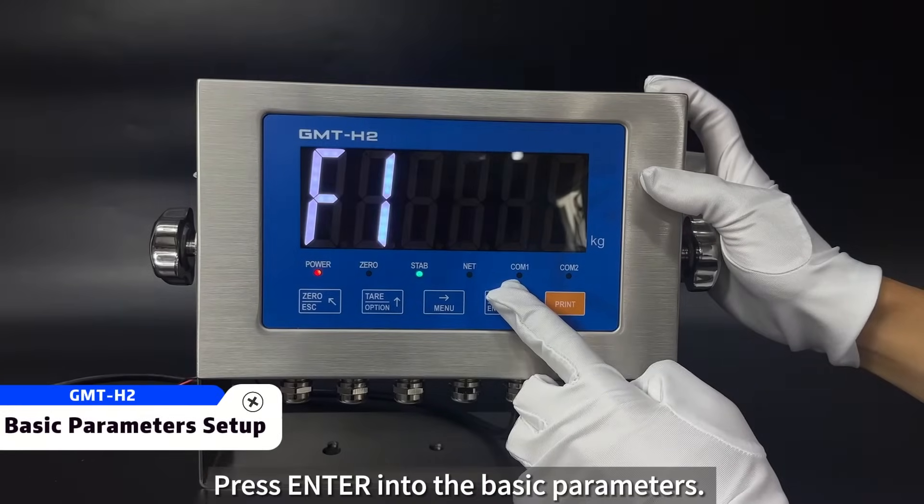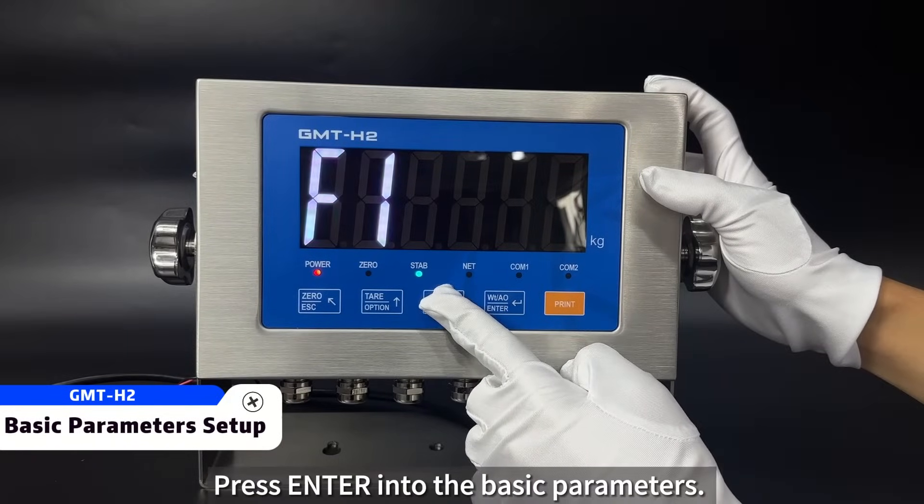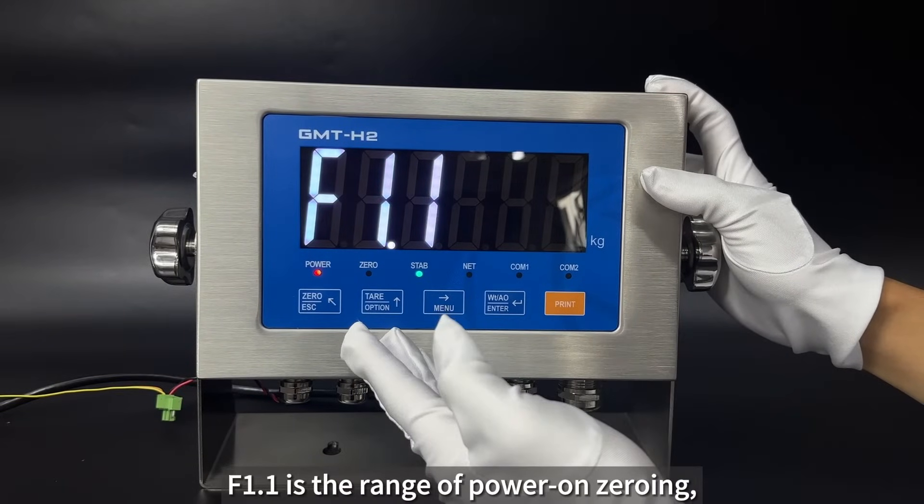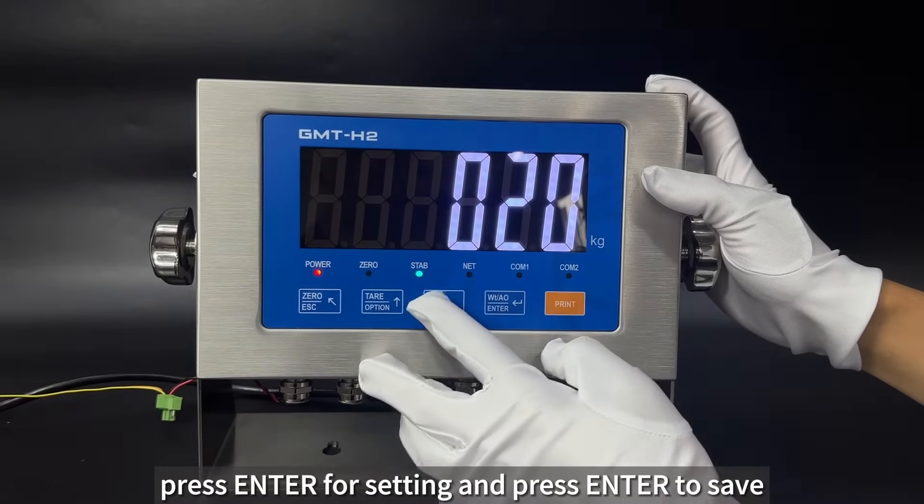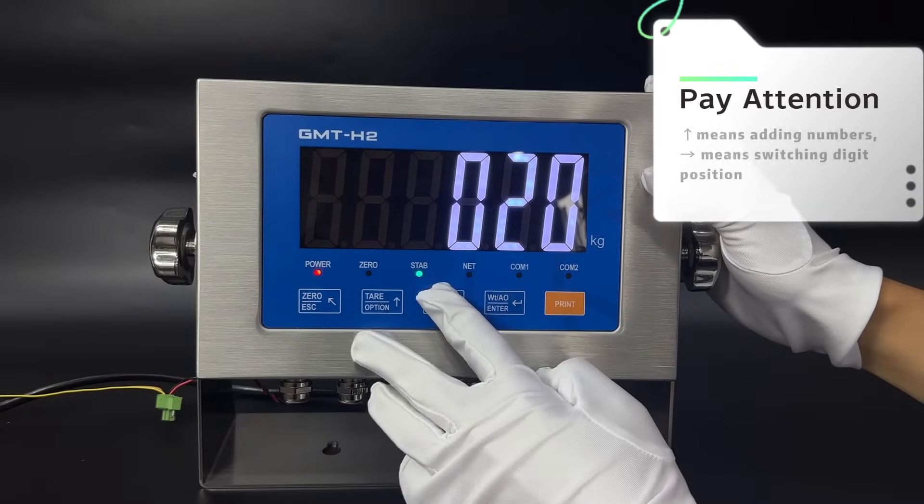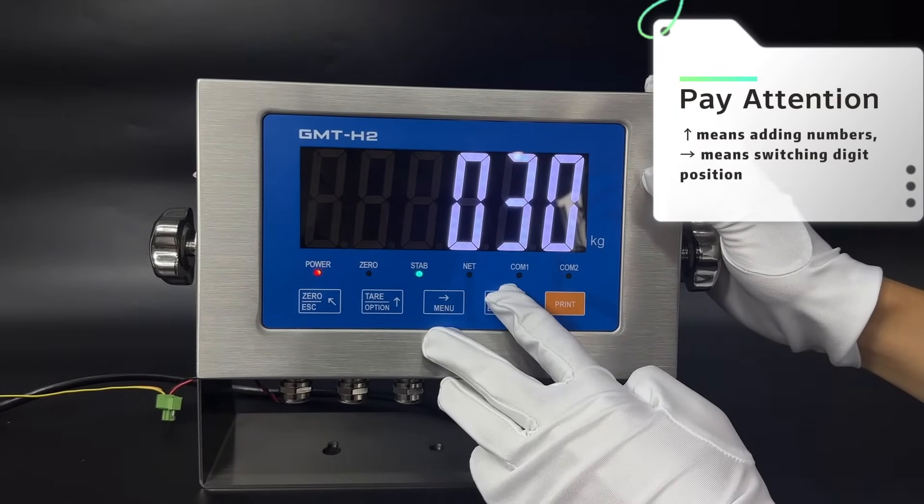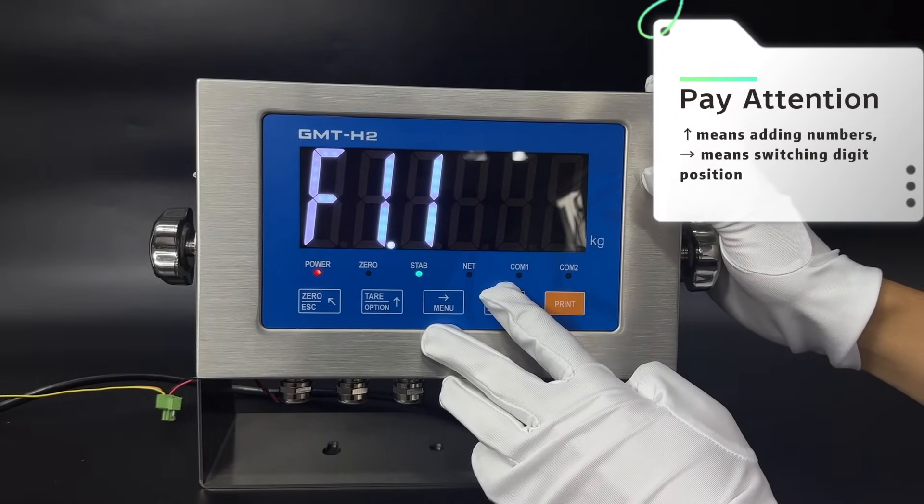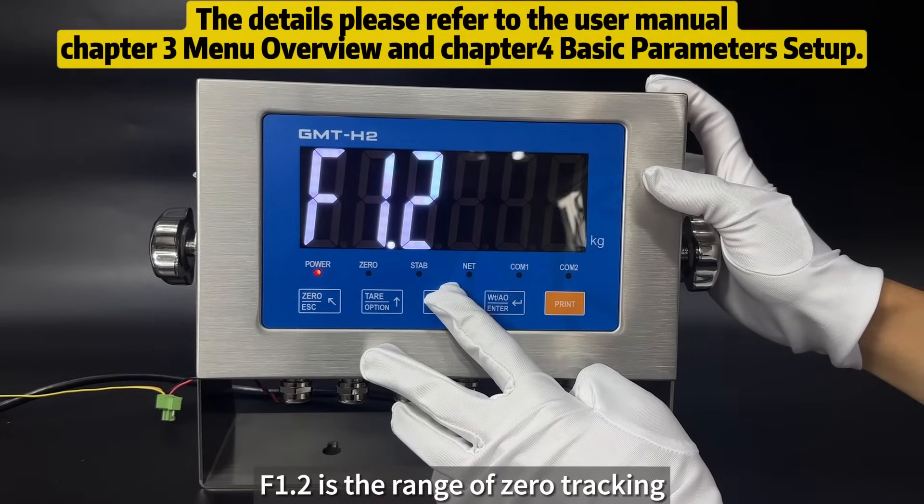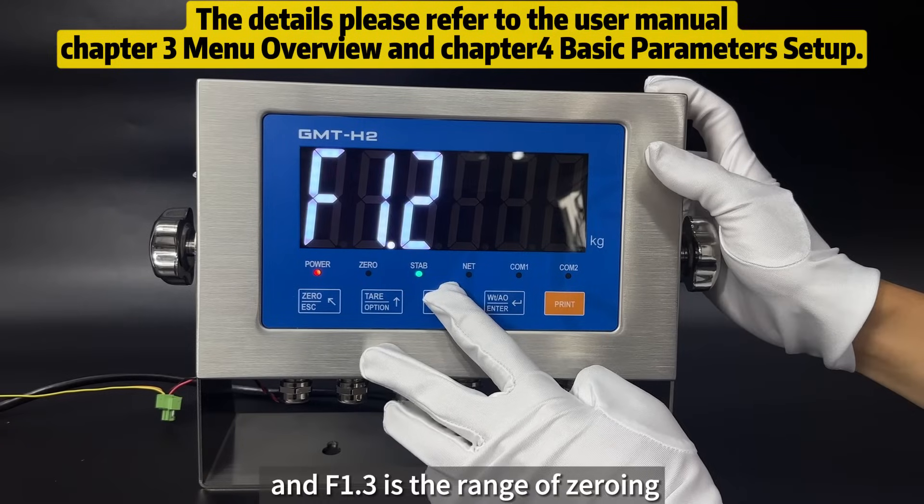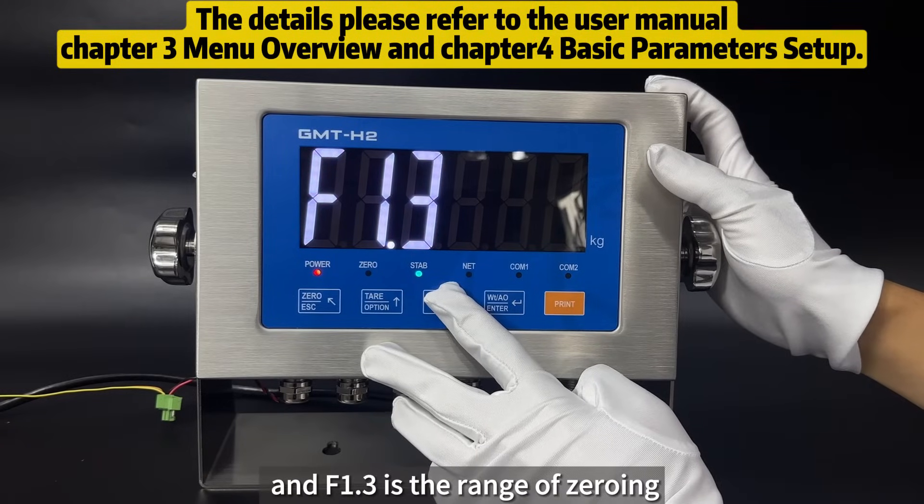Press Enter into the Basic Parameters. F1.1 is the range of power on zeroing. Press Enter for setting and press Enter to save. F1.2 is the range of zero tracking. And F1.3 is the range of zeroing.